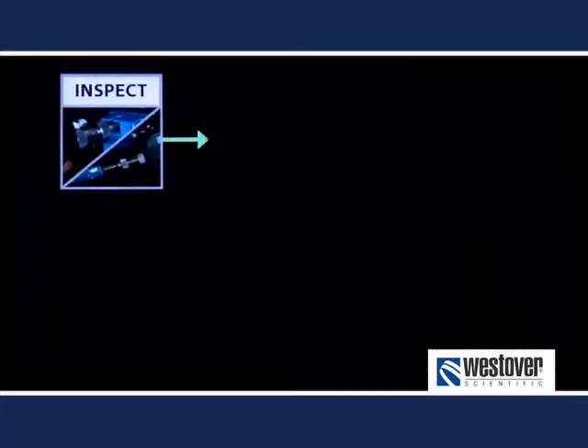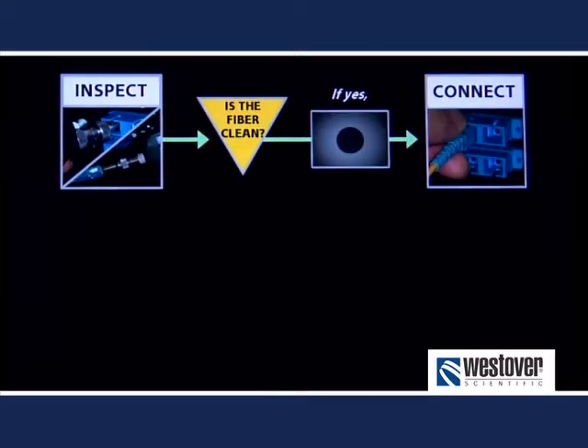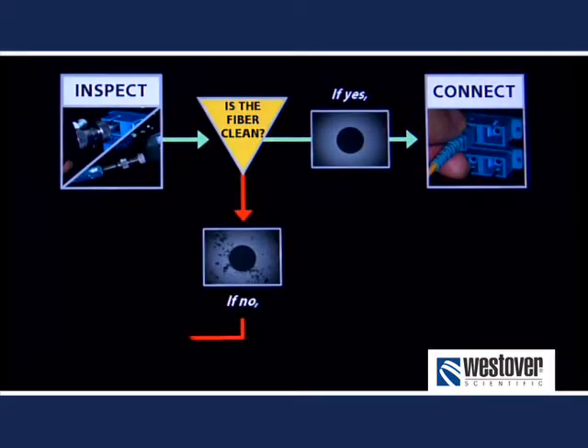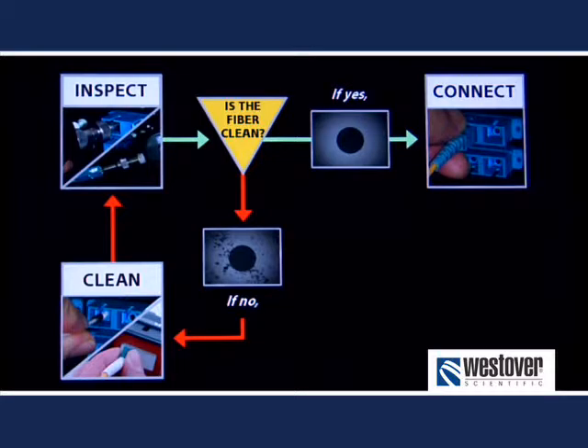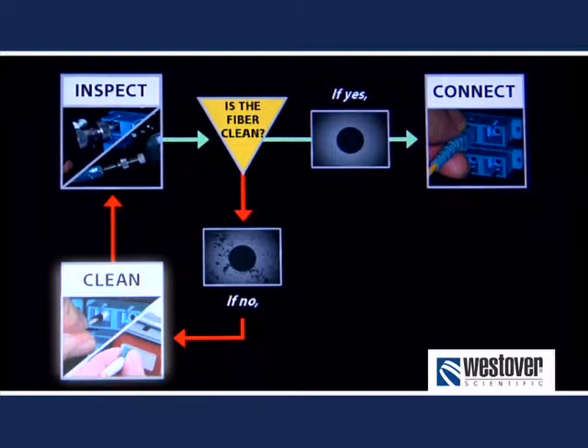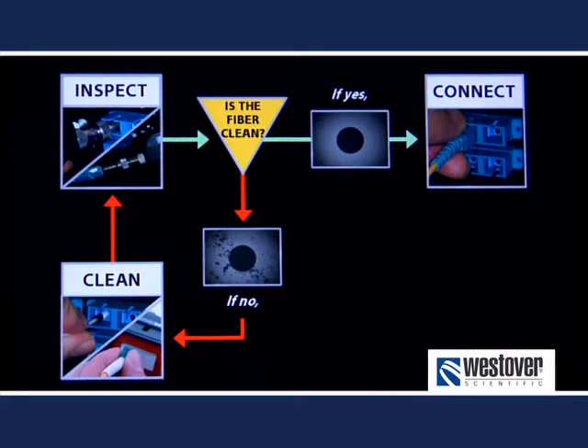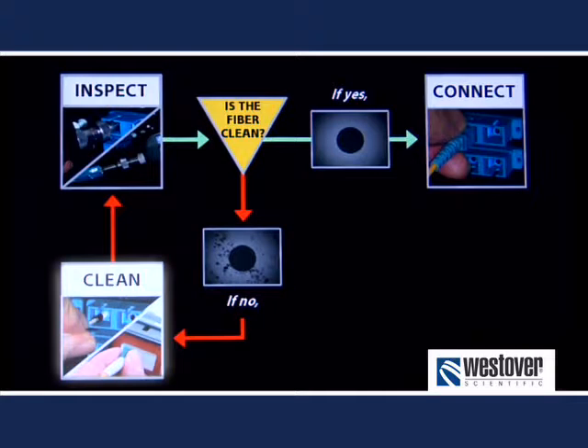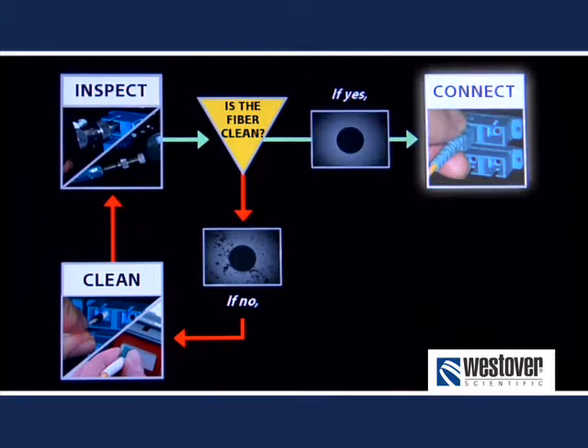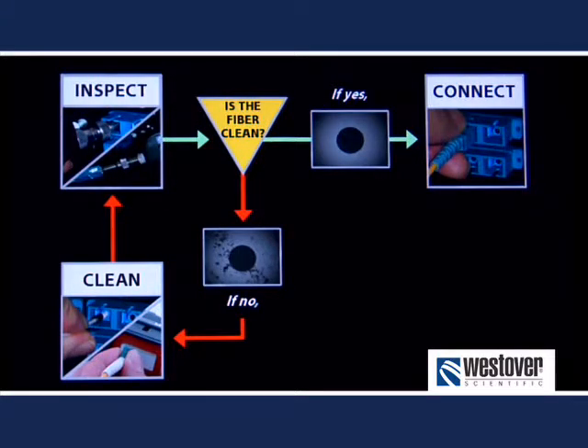In general, you do not want to clean until you have first inspected. The cleaning process is not perfect and can actually introduce dirt onto a clean connector. The correct process is inspect, clean, inspect, and repeat if necessary. If the fiber is clean at any inspection, it is ready to be put into service. Remember, it is critical to inspect both sides of the interconnect before mating.